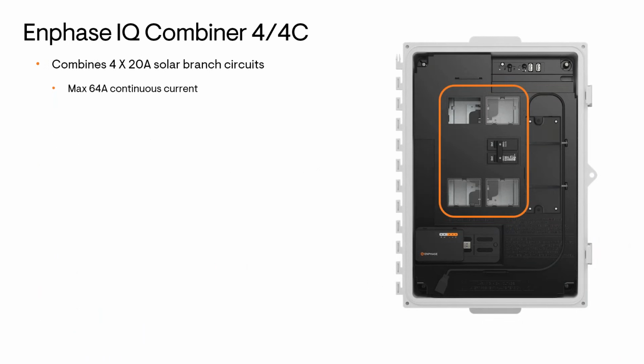The IQ Combiner 4 and 4C houses the breakers for the solar system branch circuits. It also houses the IQ Gateway, formerly called the Envoy, the communications kit, and cell modem. So how is the IQ Combiner 4C different from the 3C? The difference is that it accommodates hold-down kits for all 4 breakers. Now, why is this needed? Since the IQ8 is a multimode inverter, which means it can grid form, it can potentially deliver power or energize the conductors even if it's disconnected from the grid.